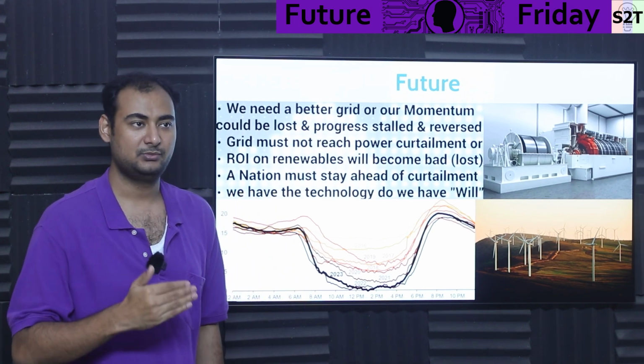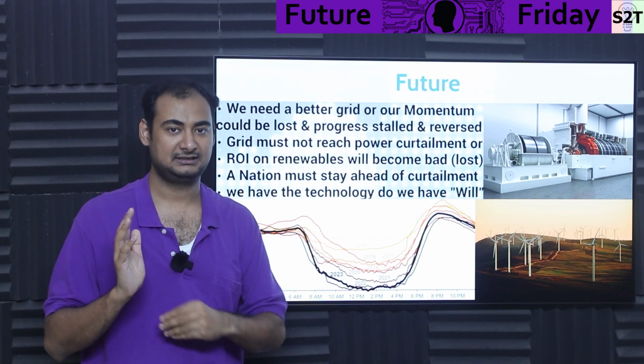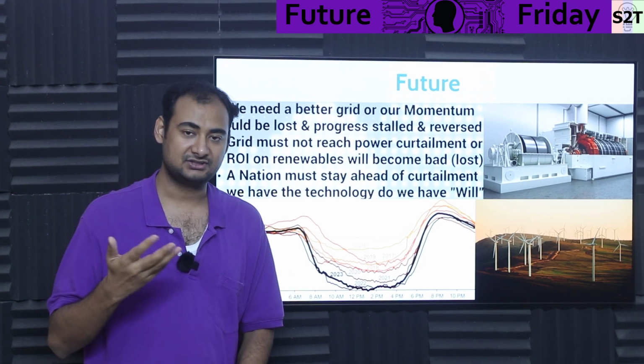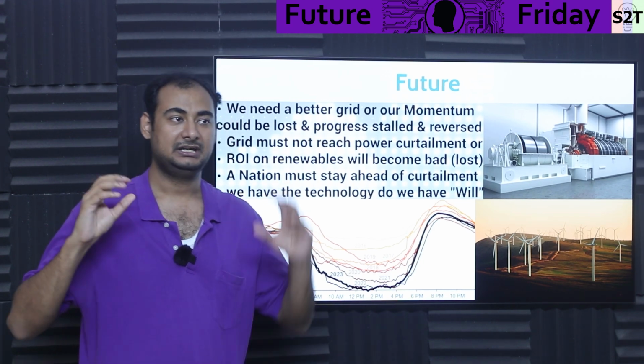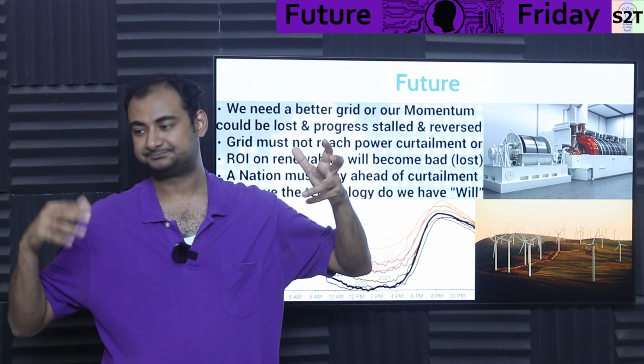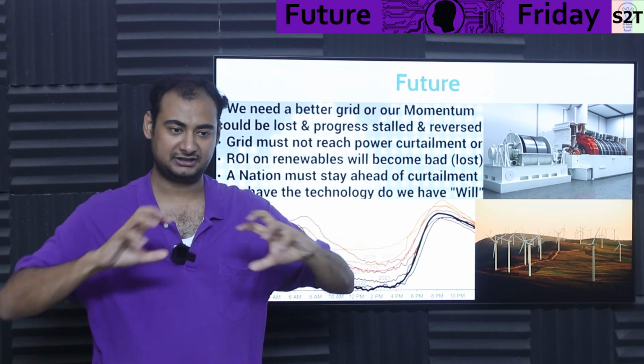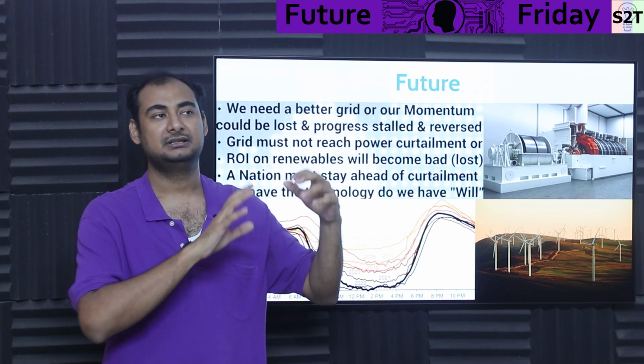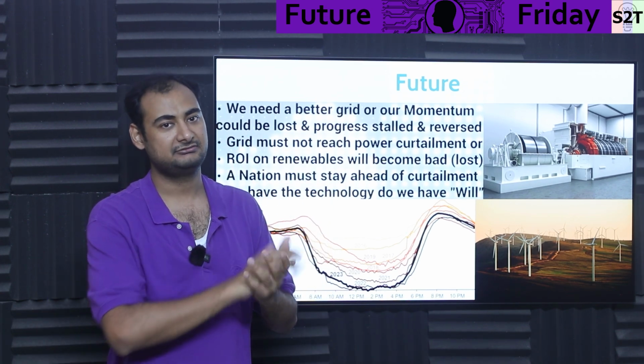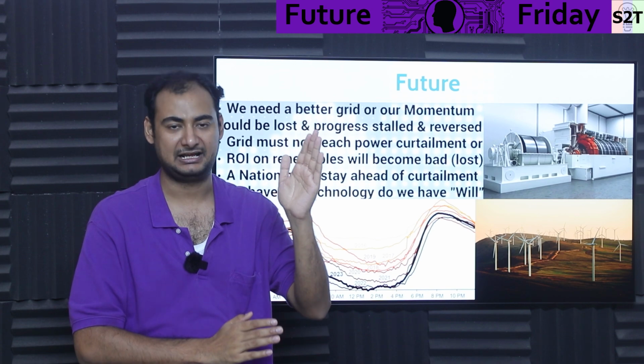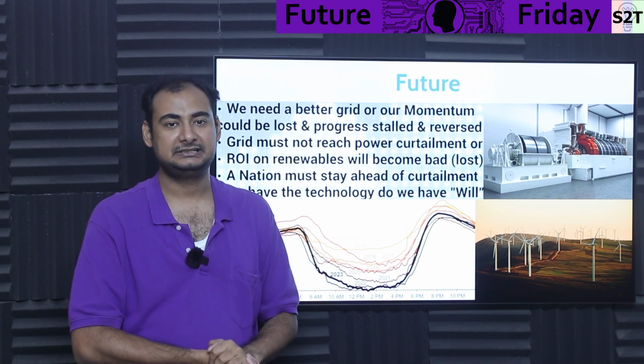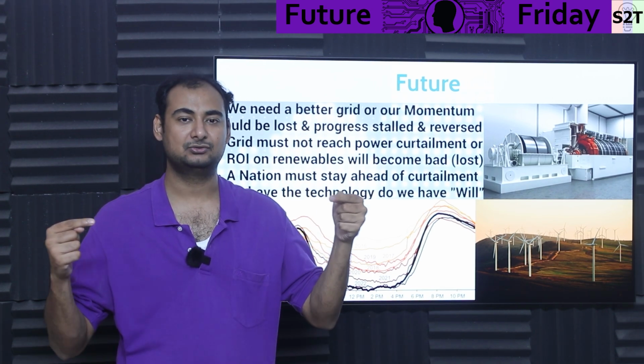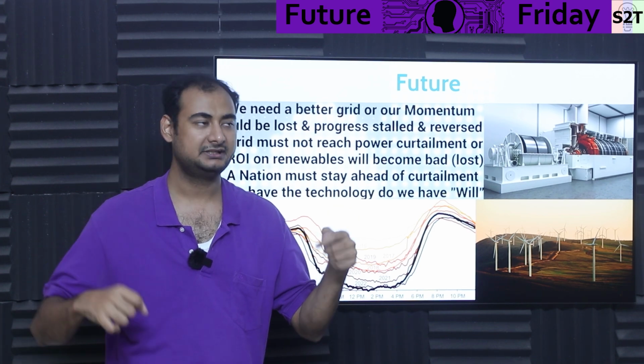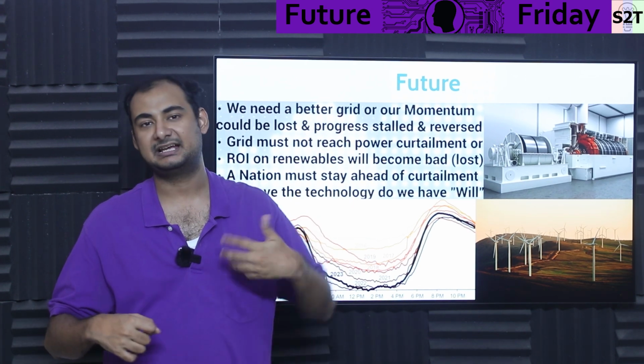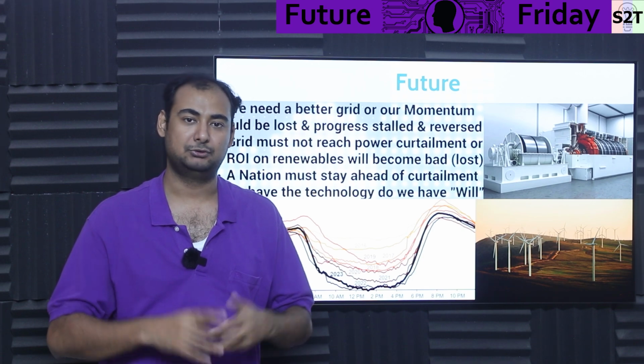And it did its best - the computer did its best to keep the RPM locked. Was it possible? Yes. It acted as an inertia, so if the turbine started to speed up, the resistance from the generator gave enough resistance that computer control could change the blade angle. But then it created an issue: you're literally fighting two forces - the inertia in that magnetic field and the inertia of the wind, that big ass mass.